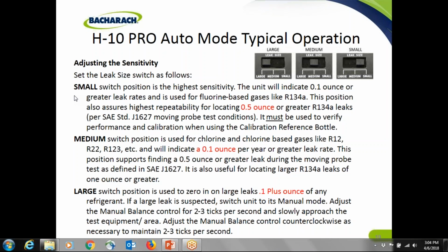If a large leak is suspected, switch the unit to the manual mode, adjust the manual balance control for 2 to 3 ticks per second, and slowly approach the test equipment area. Adjust the manual balance control as necessary to maintain 2 to 3 ticks per second. So this manual balance control, you can see from this presentation, you're going to adjust it sometimes clockwise, sometimes counterclockwise to get that 2 to 3 ticks per second.